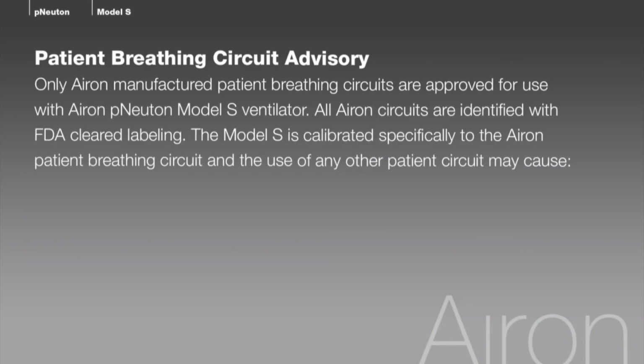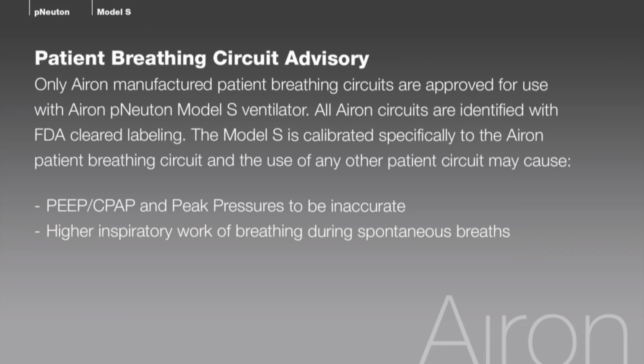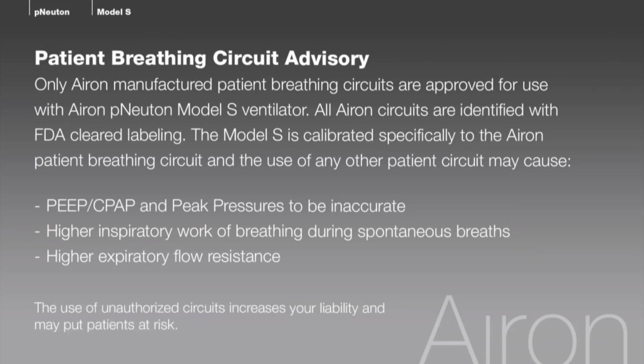Please note, only Airon manufactured patient breathing circuits are approved for the use with the Newton S ventilator. All Airon circuits are identified with FDA-cleared labeling. The Model S is calibrated specifically to the Airon patient breathing circuit, and the use of any other patient circuit may cause PEEP, CPAP and peak pressures to be inaccurate, higher inspiratory work of breathing during spontaneous breaths, higher expiratory flow resistance. Our patient circuits are competitively priced. The use of unauthorized circuits increases your liability and may put patients at risk.